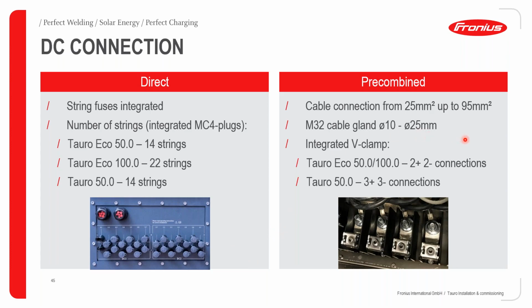Then having a look at the pre-combined, the cable connection will be from 25 millimeters squared up to 95 millimeters squared. M32 cable gland from 10 millimeter diameter up to 25 millimeter diameter. With the pre-combined option, you will have to go for the integrated V-clamps. This will be on the DC side. For example, with the Tauro Eco 50 kilowatt and 100 kilowatt, because they only have one tracker, we have two positive connections and two negative connections on the V-clamps. This is an example of that over there, so your two positives and your two negatives. However, if you are going to go for the Tauro 50 kilowatt, the Tauro with three trackers, you will have three positive and three negative connections for the pre-combined option.